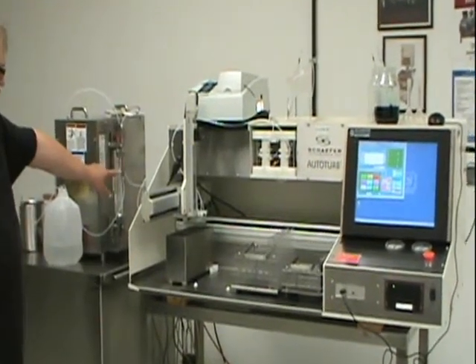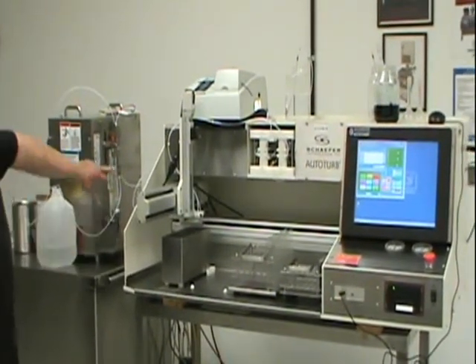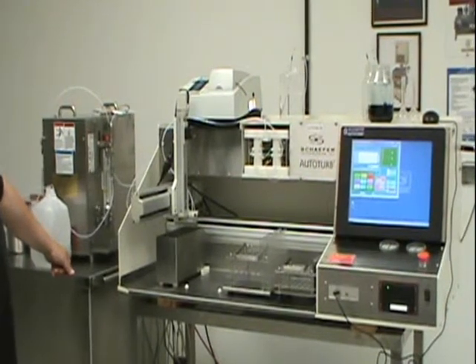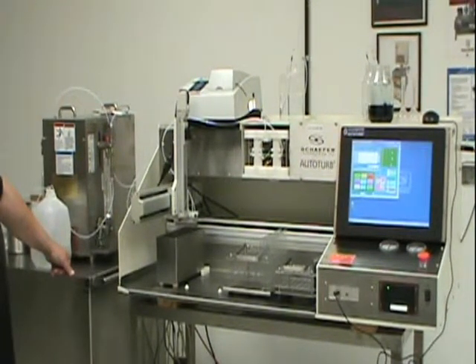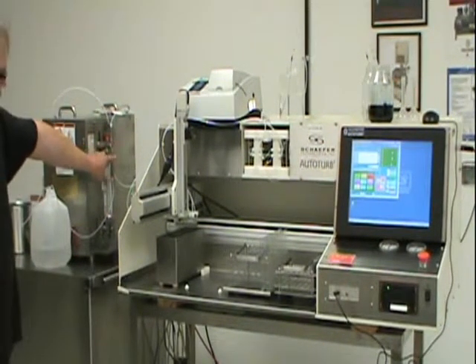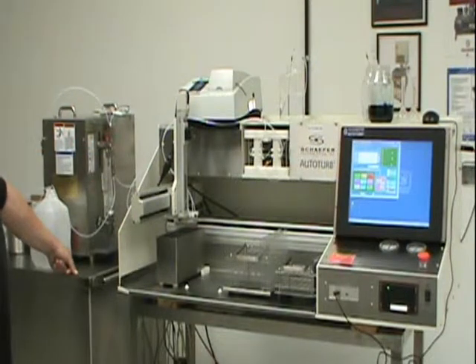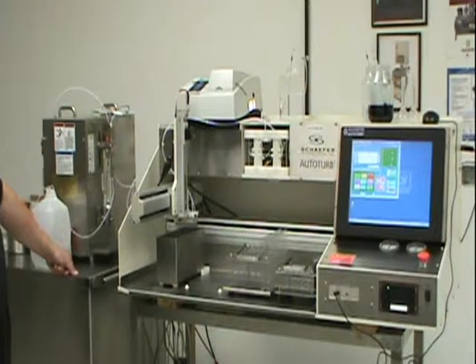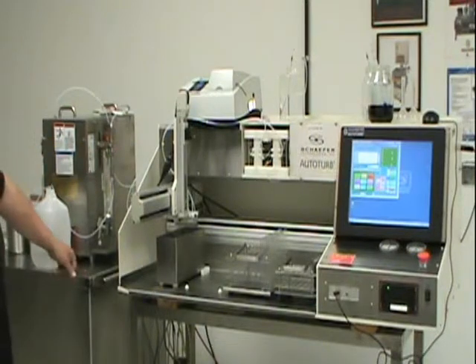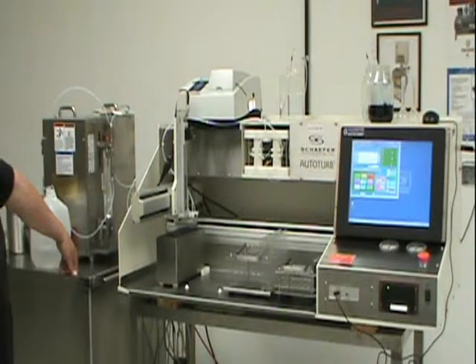We check to make sure there's no air bubbles drawn in from any loose spots, especially after the system's been sitting for a while. These paper washers can dry out and then they'll cause air checks. All I do there is just moisten it down, let it wait a couple minutes and then go, and it usually fixes that.